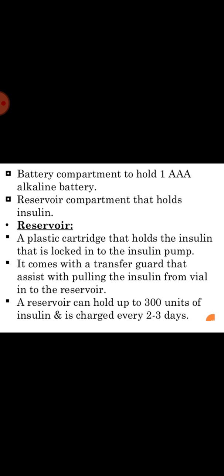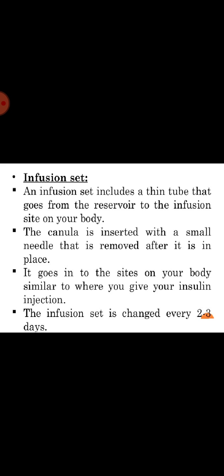The reservoir is nothing but a plastic cartridge which holds the insulin that is locked into the insulin pump. It comes with a transfer guard that assists in pulling the insulin from the reservoir. The reservoir can hold up to 300 units of insulin and is changed every 2 to 3 days.